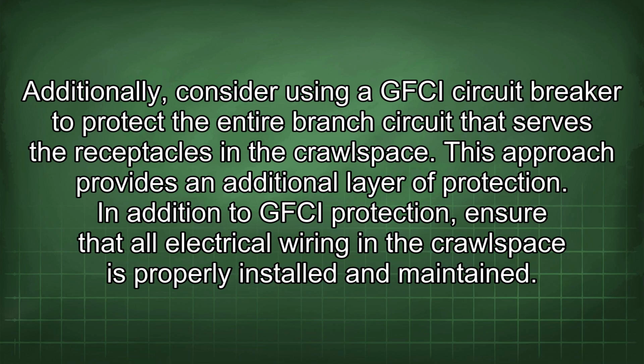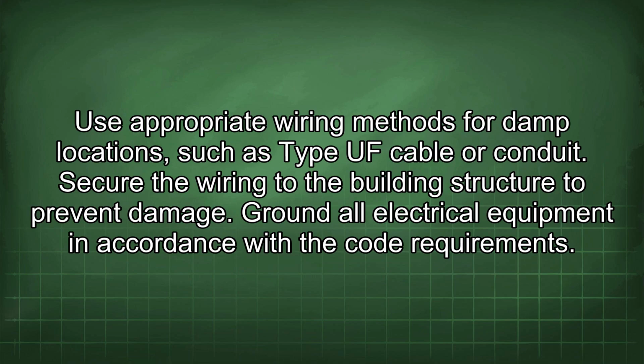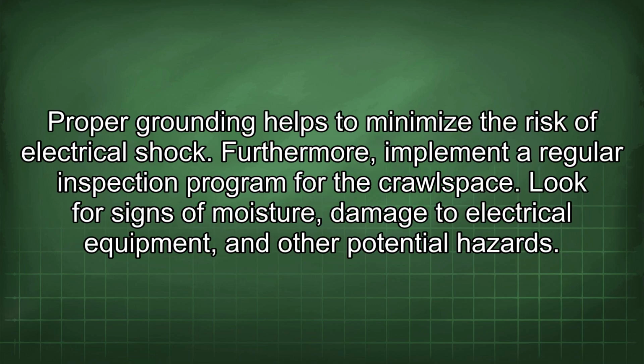In addition to GFCI protection, ensure that all electrical wiring in the crawlspace is properly installed and maintained. Use appropriate wiring methods for damp locations, such as Type UF cable or conduit. Secure the wiring to the building structure to prevent damage. Ground all electrical equipment in accordance with the code requirements. Proper grounding helps to minimize the risk of electrical shock. Furthermore, implement a regular inspection program for the crawlspace.